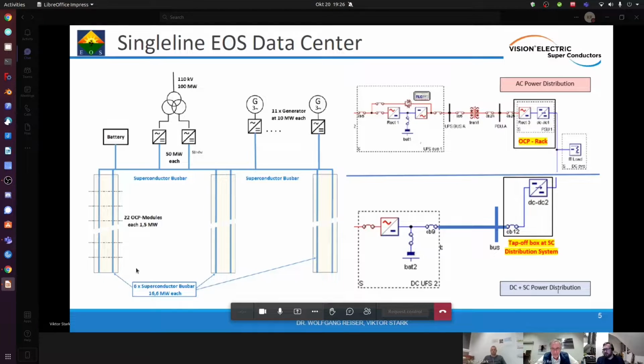Let me rephrase this because you mentioned a lot of very good points. One obviously is that traditional DC supplies in data centers usually have a big problem because we have data halls about 200 meters long, or even a little longer, and from the start of the hall back to the end, you would have a massive voltage drop, right? It's not easy to supply the same level over such a long length traditionally, but with superconductor busbars you will have the identical voltage and supply stability over the whole length, correct?